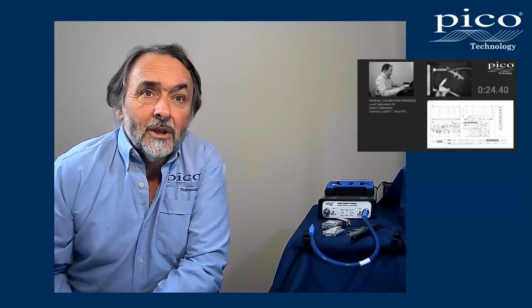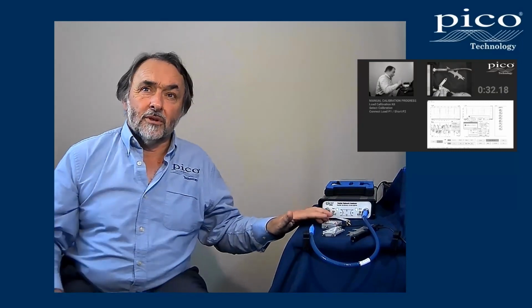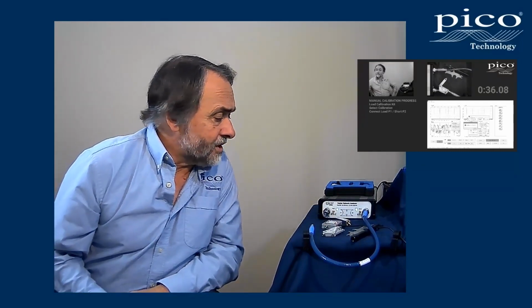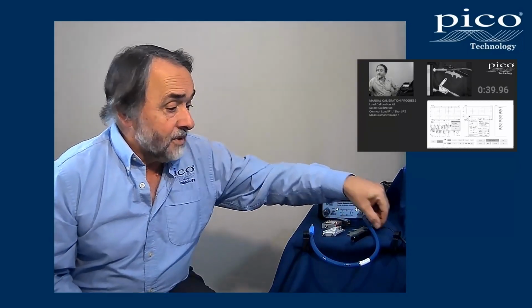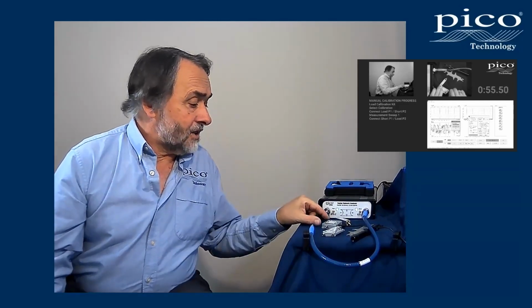Okay, so while he gets on with that, by the magic of video recording, we'll use our e-calibration device in parallel and see how we get on with this. Okay, so the short, open, load and through that we've done our manual calibration with, those parts are all within this module, along with microwave switches, so that we can automatically, over USB control, select the short, open, loads and throughs when we need to. The device also stores its own characterization data, so that is in there too, and can be read over the USB interface.